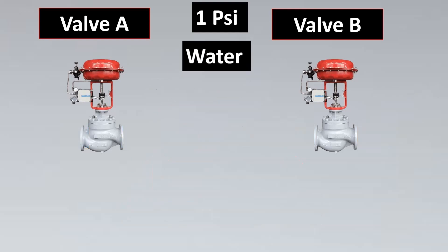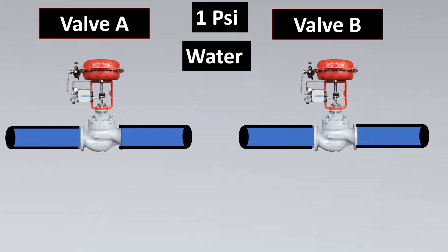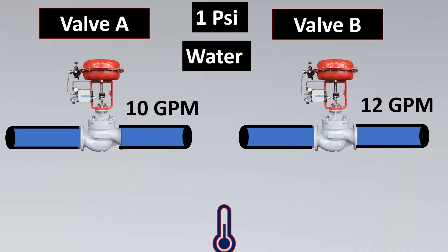Let us select water, because water is one of the most available substances and very easy to find at any site or vendor location. Now with the same pressure drop and the same liquid — water — for both valves, ideally I should get the same flow rate. But for this valve I get 10 GPM and for valve B I am getting 12 GPM. So there is another parameter which comes into play.